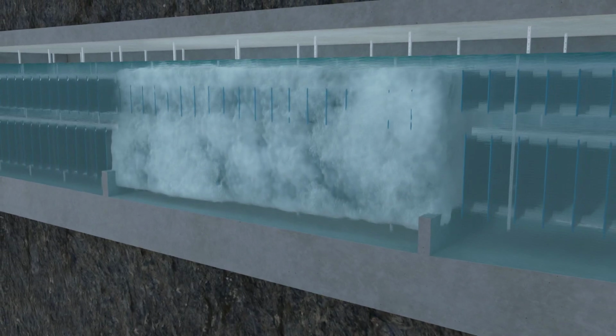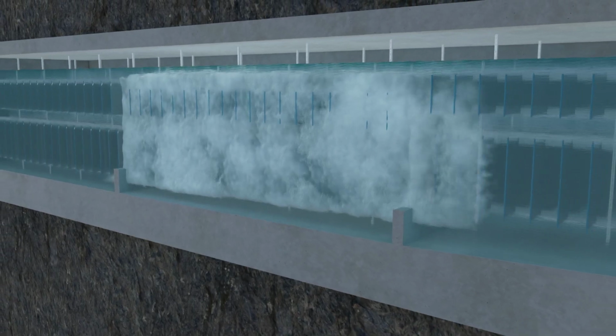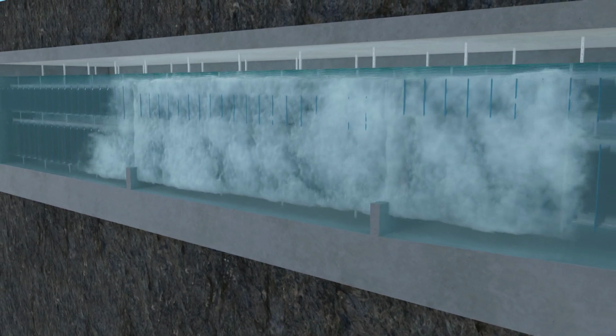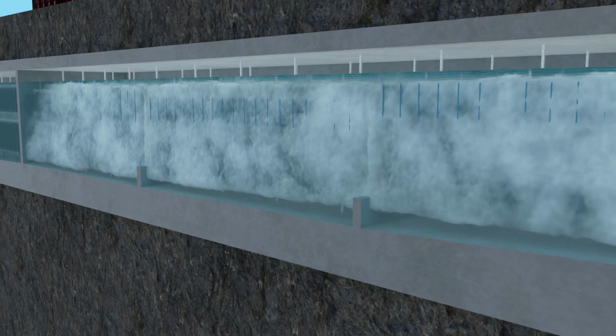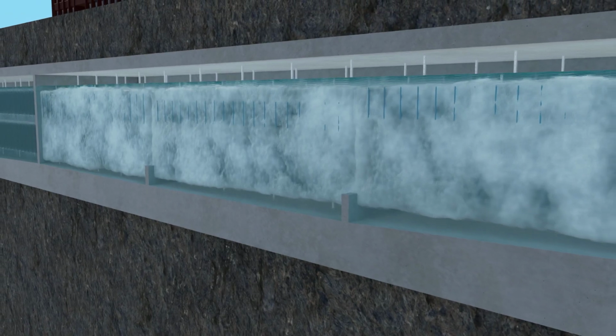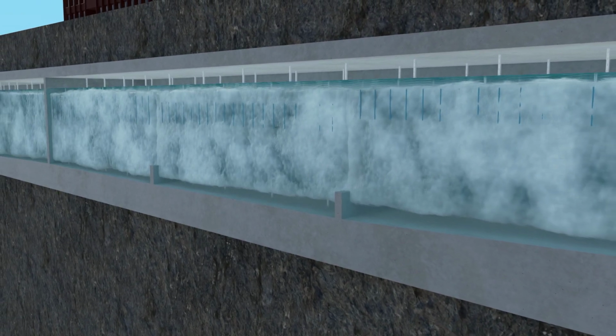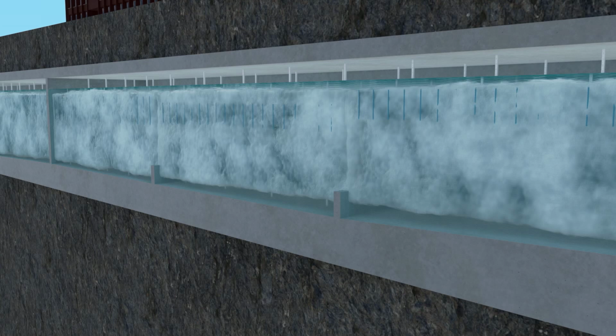By the end of the winter, 1,500 cubic meters of water have frozen into a large block. The ice can expand without bursting the tank. The formation of ice on the heat exchanger plates is one of the largest blocks of ice in Europe.